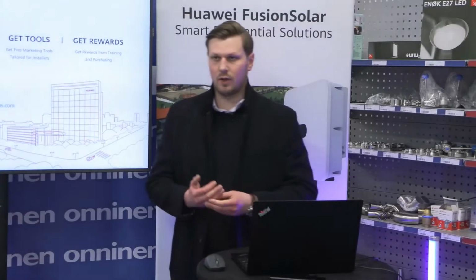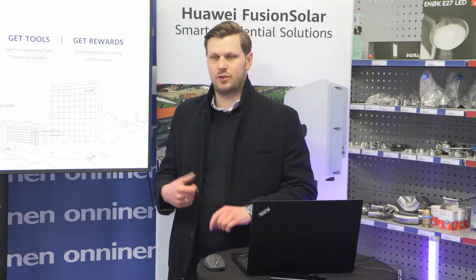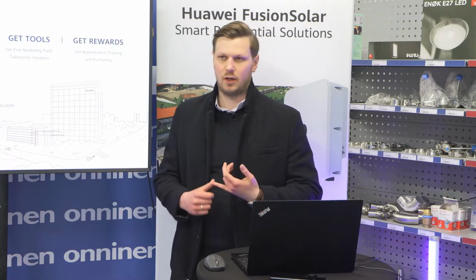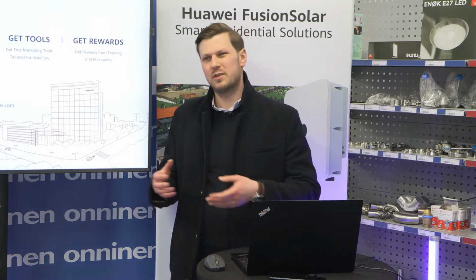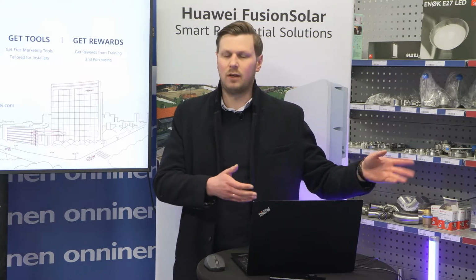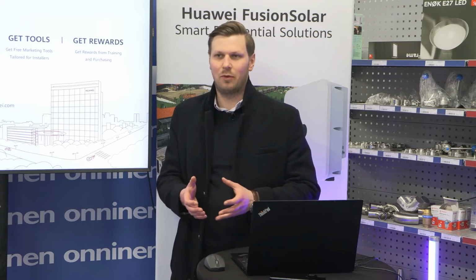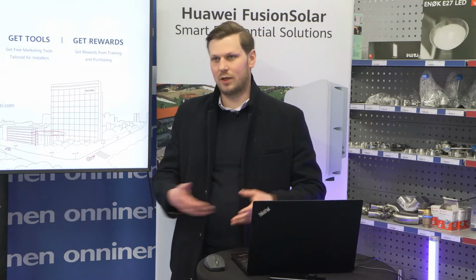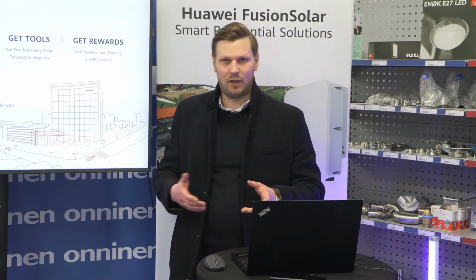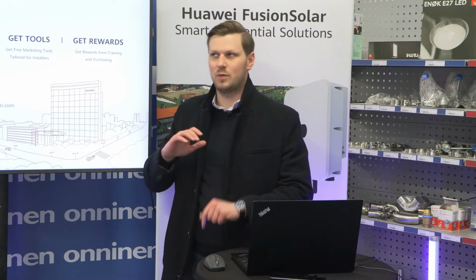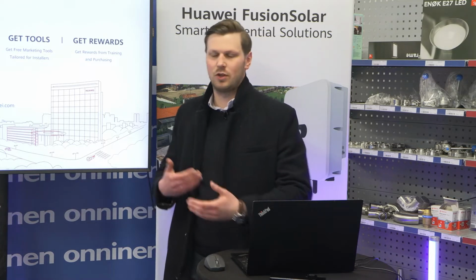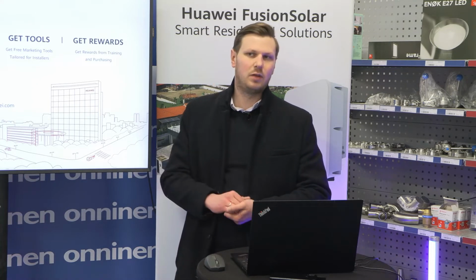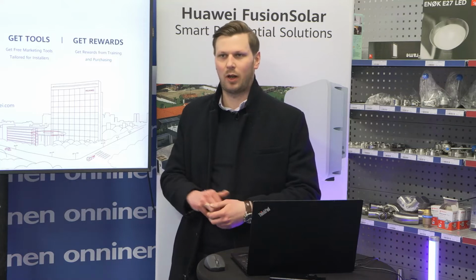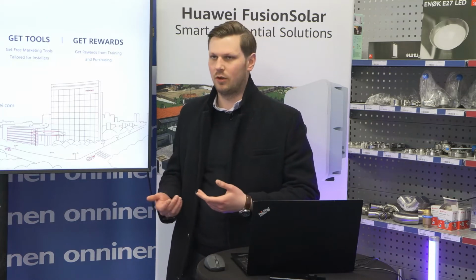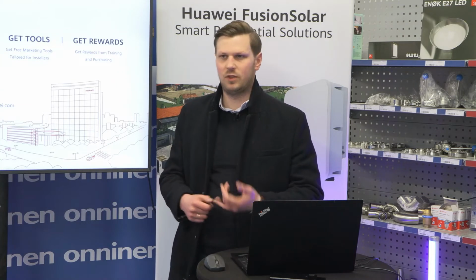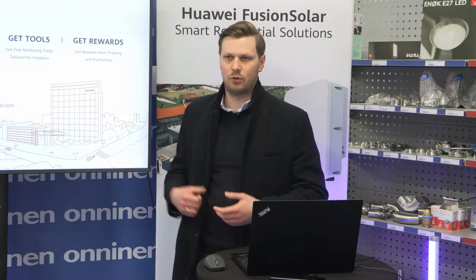Officially for the 50 kilowatt inverter, which is very popular in Estonia, the manufacturer supports two ways of communication with the outside world: the 4G dongle and the smart logger. The smart logger is for much bigger projects, like when you have more than 10 inverters. I can also provide info on connecting the regular dongle, the wireless fast Ethernet dongle, though it's not officially supported by the manufacturer yet. The hardware is prepared, the software is almost ready, but the manufacturer doesn't support it yet. Still, it's possible. We've had many different projects in Estonia over the last 2 years where about 90% work with the 50 kilowatt inverter using the regular WLAN fast Ethernet dongle. So for the series of 50-60 kilowatt inverters, you can use whatever is available from Huawei to communicate with the outside world.